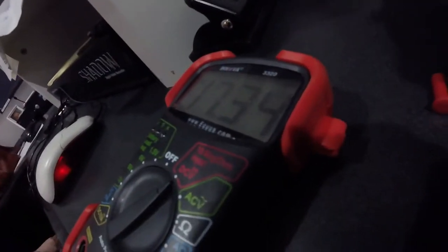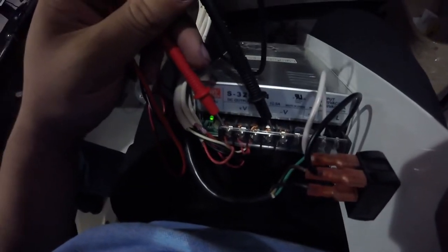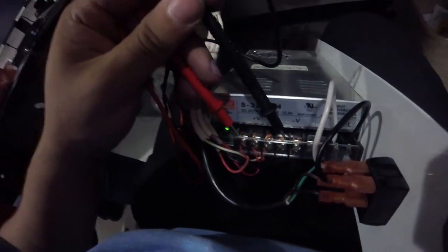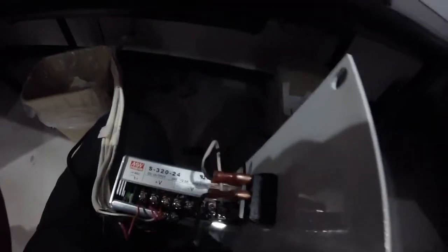We're replacing a power supply for a CCTV system. The old power supply is only outputting 17 volts which is not enough to power the TV monitors. There's monitors and also cameras in the store. The cameras can run off 12 volts, but the power supply needs to send 24 volts to the TV or we don't have a picture.